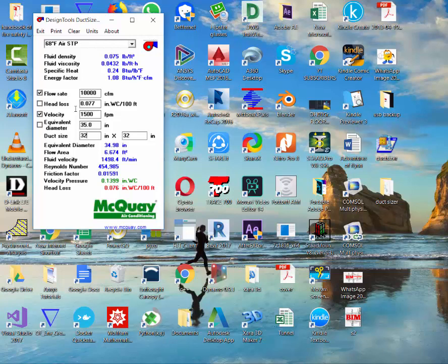That whenever you use the duct sizing software, the width to height or height to width should always be within a ratio of 1 to 4. It should not go... the ratio is 0.25, or 1 by 4 equals 0.25.